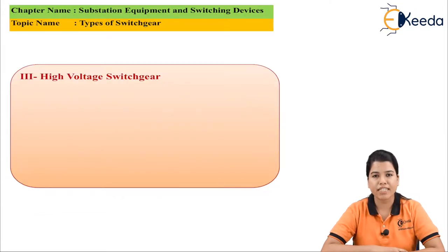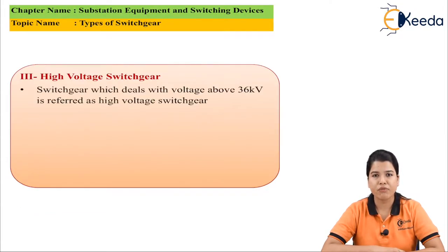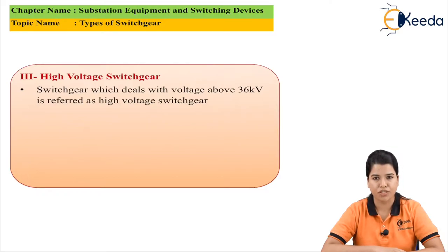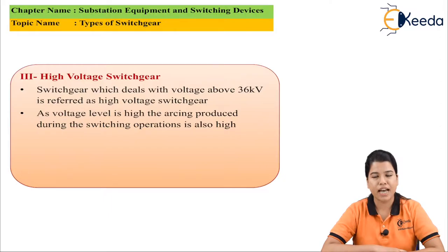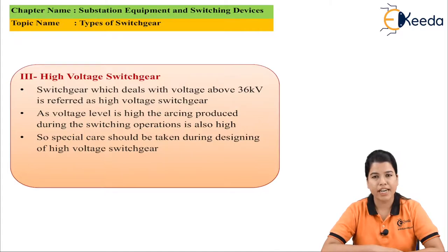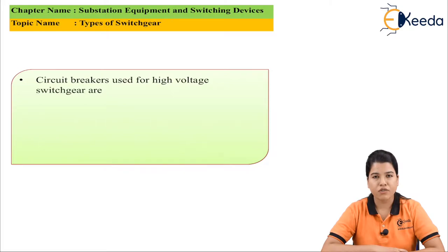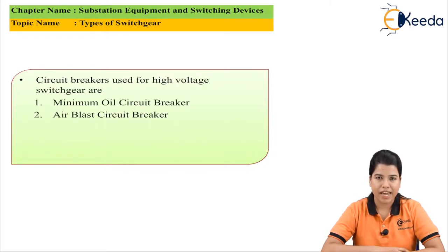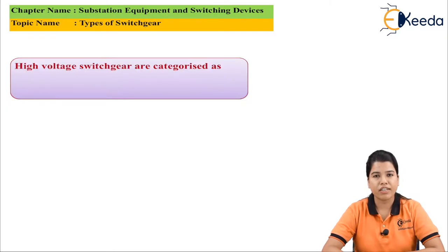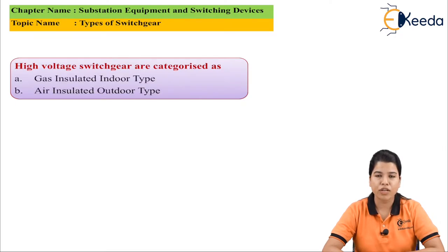The next type is high voltage switchgear. Switchgear which deals with a voltage rating of 36 kV and above is called high voltage switchgear. As the voltage level is high, the arc produced during switching is also very high, hence special care should be taken while designing the operators of the switchgear. The circuit breakers used for this type are minimum oil circuit breaker, air blast circuit breaker, and SF6 circuit breaker. High voltage switchgear is further divided into gas insulated indoor type and air insulated outdoor type.